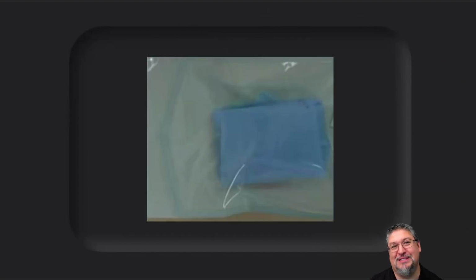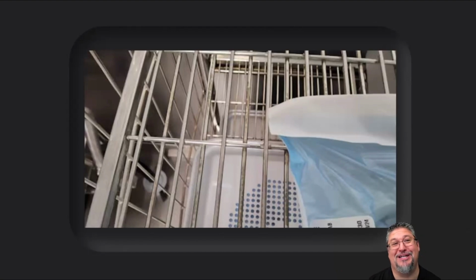This is a wrap inside of a peel pouch. A wrap is a form of a sterile barrier that has its own instructions for use. A peel pouch is another sterile barrier that has its own IFUs. And you cannot put one of these inside of the other. You shouldn't put a wrap inside of a rigid container. You shouldn't put a rigid container inside of a peel pouch. These things individually have their own IFUs. Don't mix and match them. They're not plug and play or mix and match.